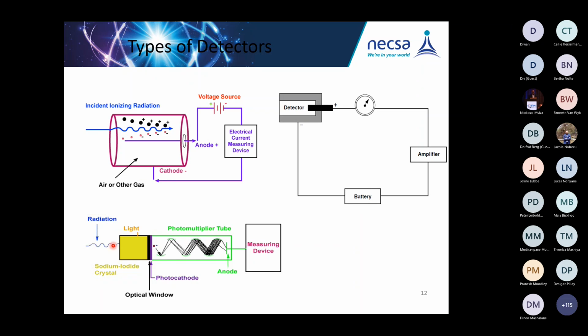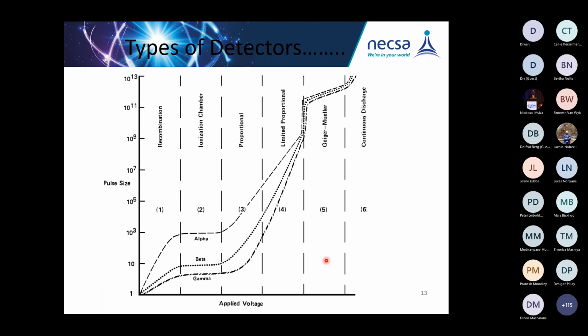This is the scintillation detector, the one with the glass that I even mentioned. And this glass is meant for the instrument which measures alpha and the beta. If you bang the probe, then this glass tube will break, and it's quite sensitive and also a bit more expensive. It might even cost you plus or minus 15,000 if it is broken. And this is the type of your ionization chamber.